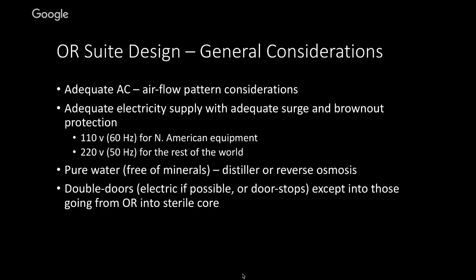We also realize, of course, that we are often in environments where the voltage is 220, but when we say it's 220, that means often that it's somewhere between 40 and 440. And so we have problems with all of our electronic equipment, our monitors, our cautery, etc., because we have to protect against both surge, the high voltage, and brownout, the low voltage. And actually, the low voltage is one of the more major problems. So one of the things that's very, very important is to sit and talk to an electrical engineer and see if you can isolate the electrical systems in these operating rooms so that neither surge nor brownout will wipe out all this equipment. As you know, we have a major problem with taking equipment from the United States, which is built for 110 volt, putting it in this environment, and then it fries very, very quickly.